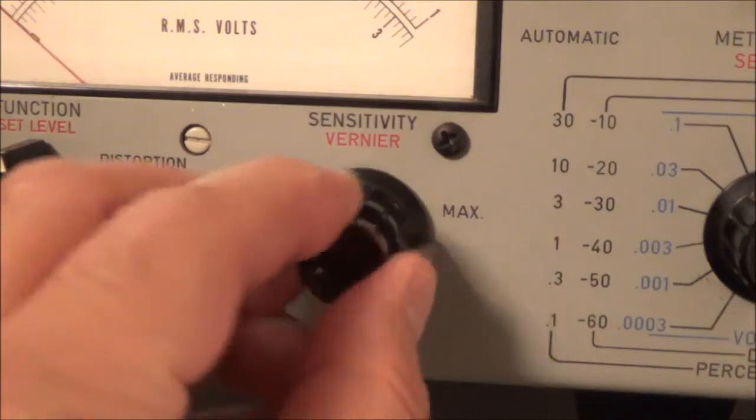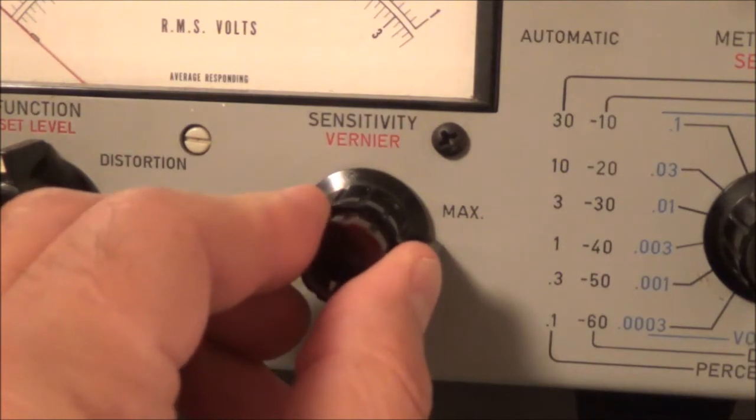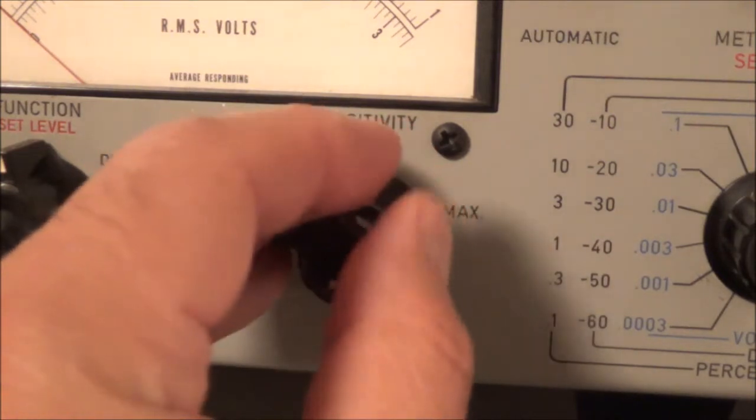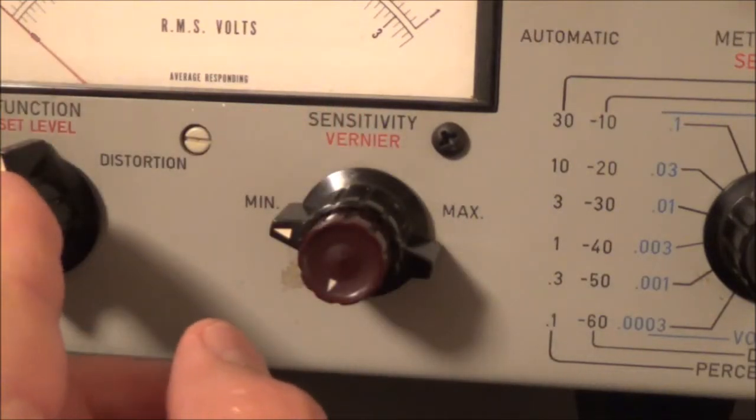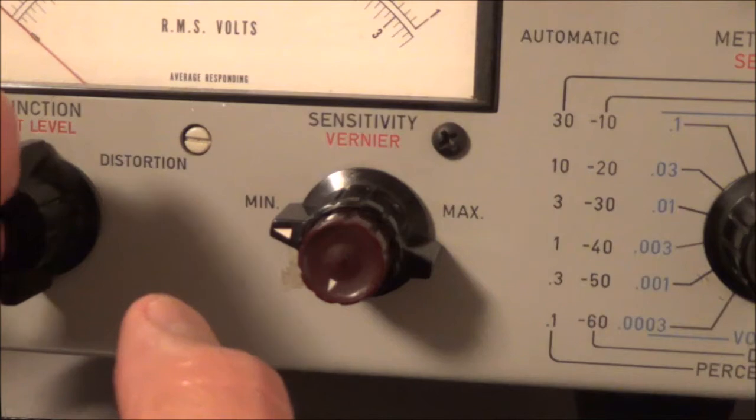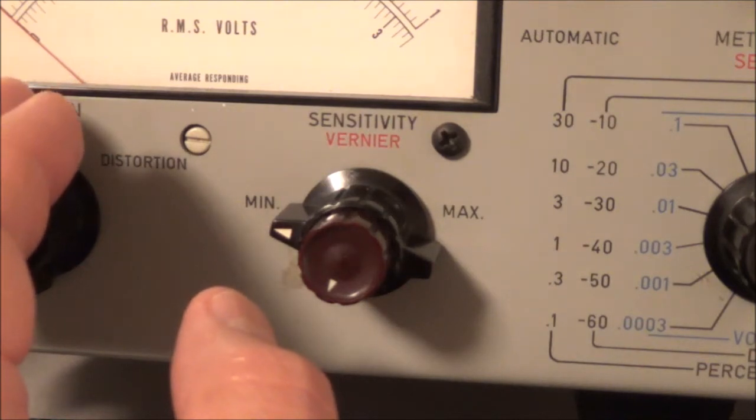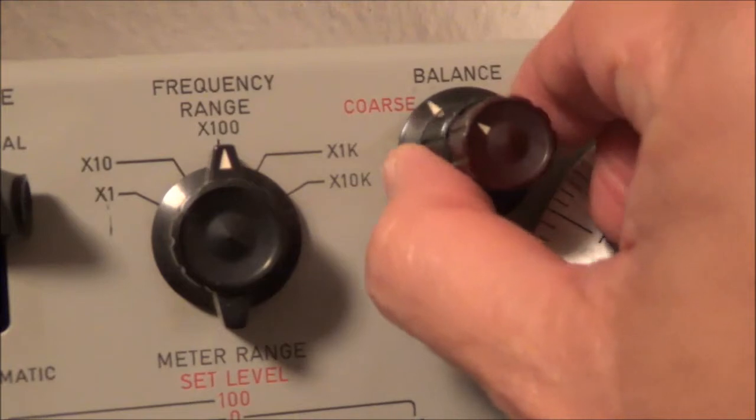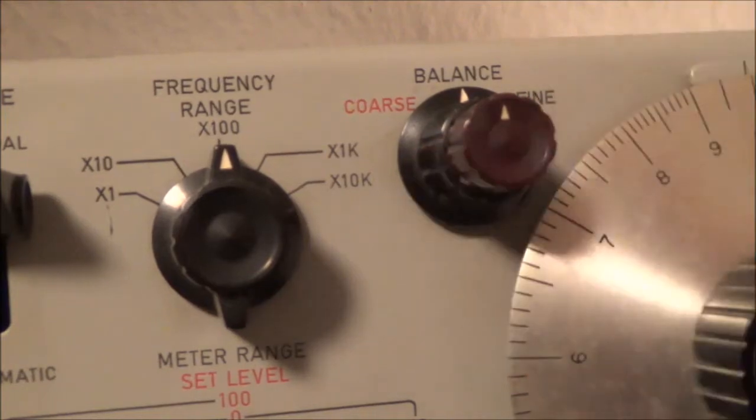So with this switch, the sensitivity switch, we set that to basically minimum, which would be counterclockwise. And this vernier control here, same thing with that. We set that counterclockwise all the way. And we got the meter switch to set level. That's the switch which we're going to use now to calibrate this thing and get it ready. And we want here the coarse and the fine controls set to the center position.